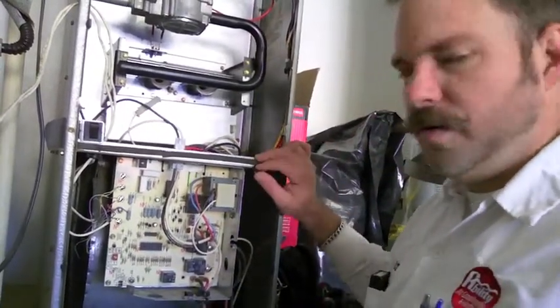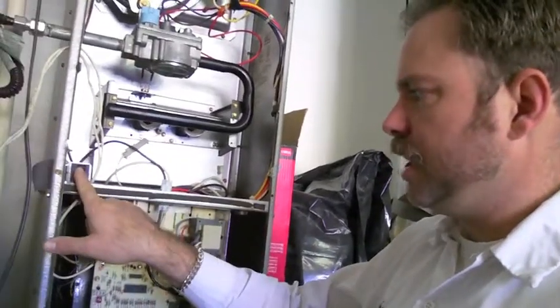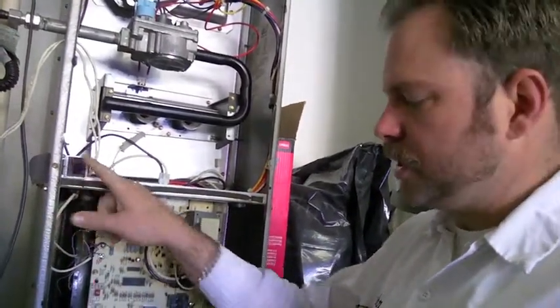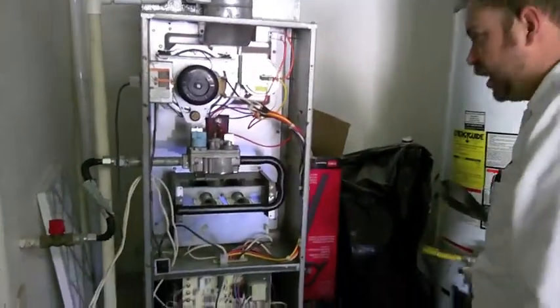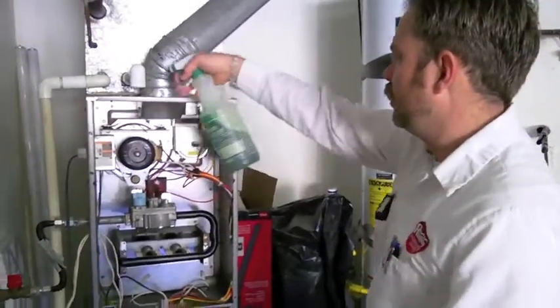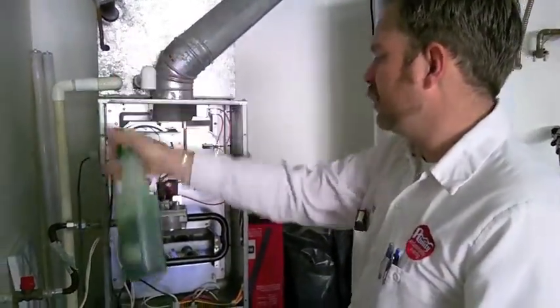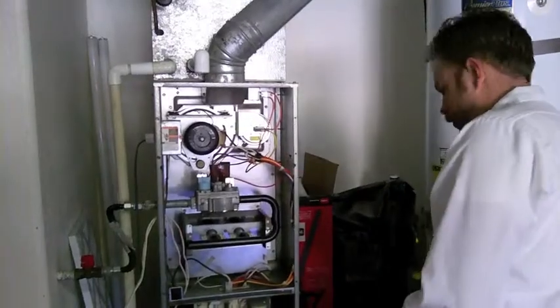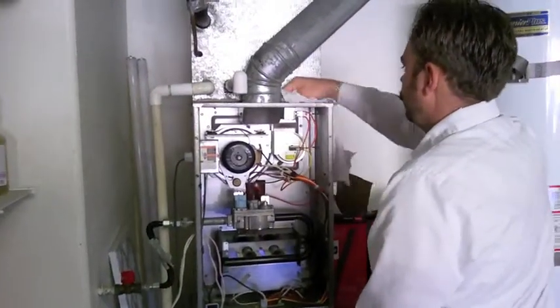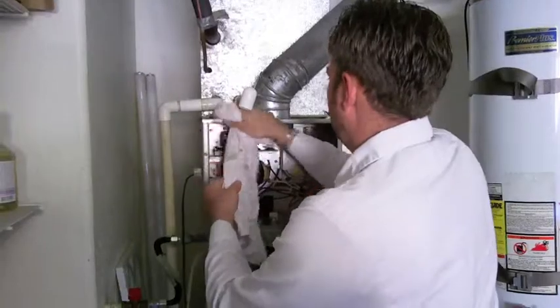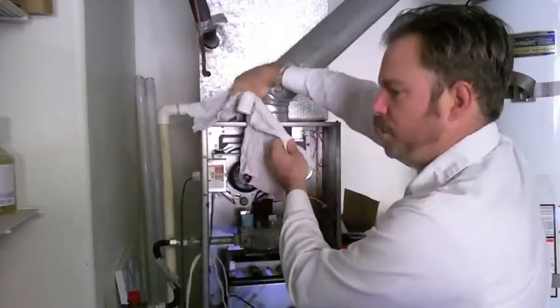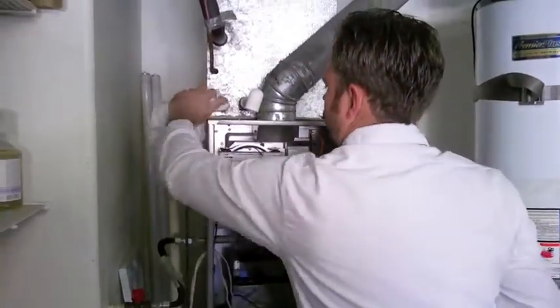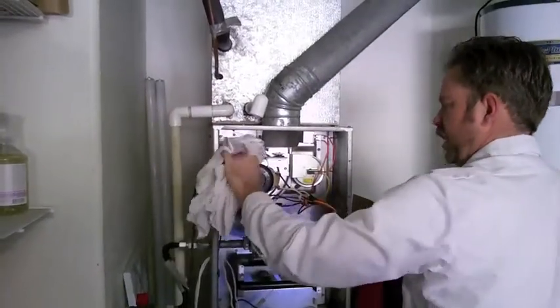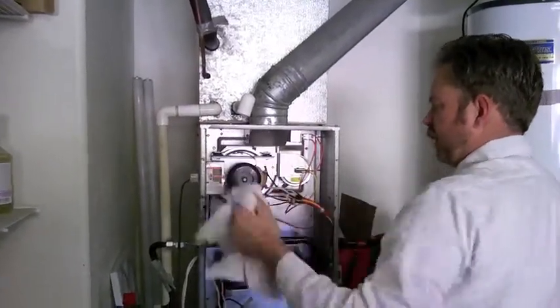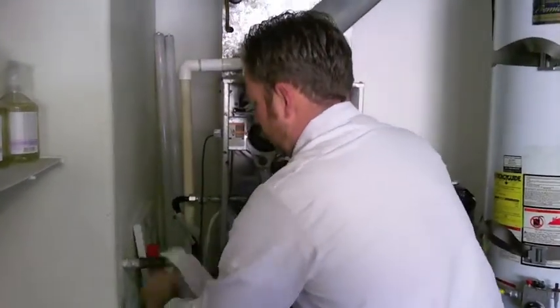Also, when I remove this door, there's this safety switch right here, and it actually shuts this furnace down, so there's no power running through this. So then after I've brushed it off, I'm going to go ahead and clean it up. I like to spray these off, and I just use a green solvent, like Simple Green will work. I get a special green solvent from the HVAC supplier myself, but it's basically the same as Simple Green.